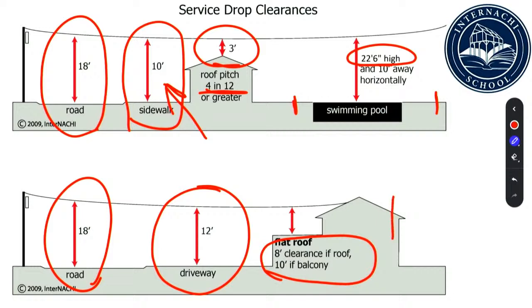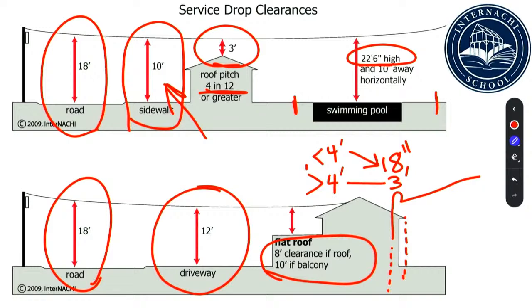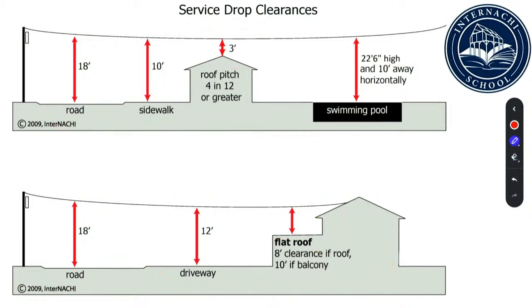Sometimes you're going to see a service mast come up and the wires come over the roof like that. Sometimes this is 18 inches and sometimes it's 3 feet. It all depends on the horizontal run over the roof. So if the horizontal run is less than 4 feet, then I could be within 18 inches. If it's greater than 4 feet, now I have to be a minimum of 3 feet over the roof. So if we look at this attachment here, compared to where the roof comes in there, either this is a very small house, or that's going to be by relation more than 4 feet of a run overhang. So that wire has to be at least 3 feet above the roof. So as it's drawn in this diagram, where it meets and comes into the roof, that's no good. It has to have a service mast that comes up and raises it up by at least 3 feet. Good stuff.